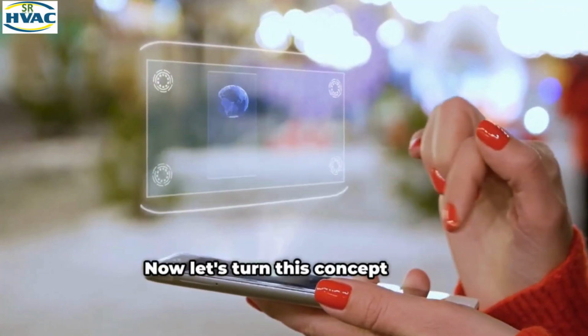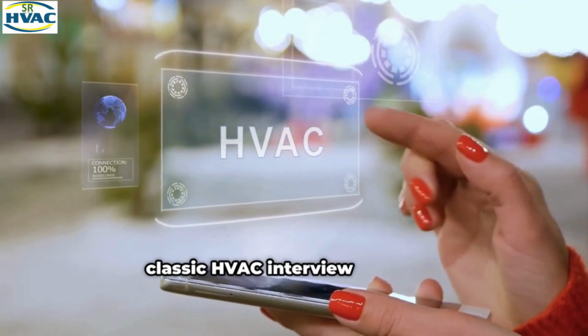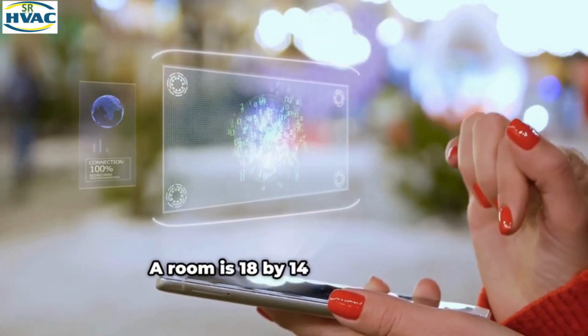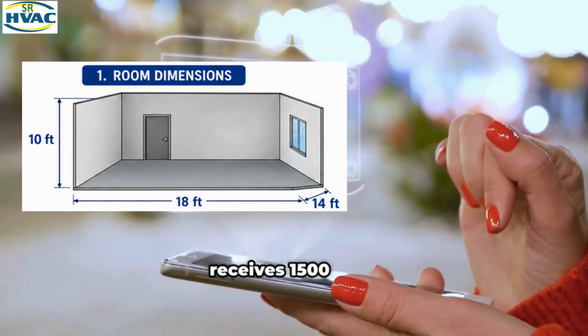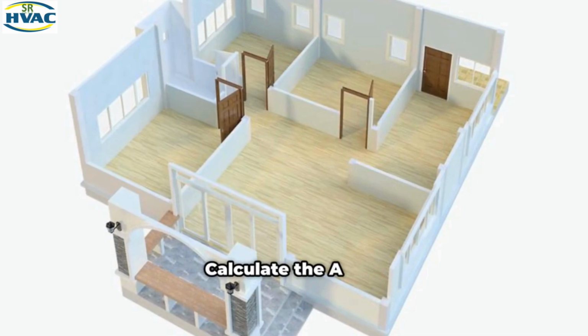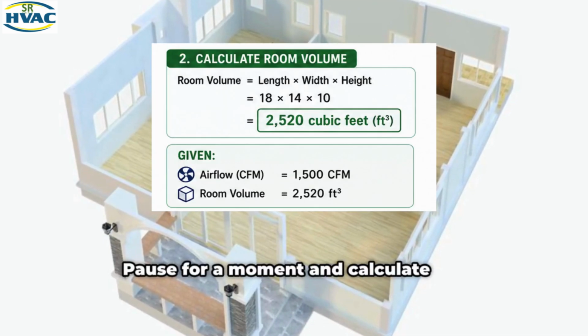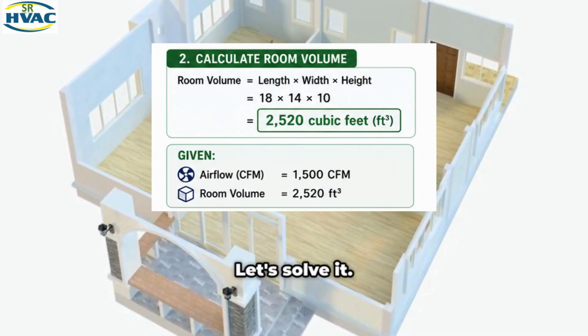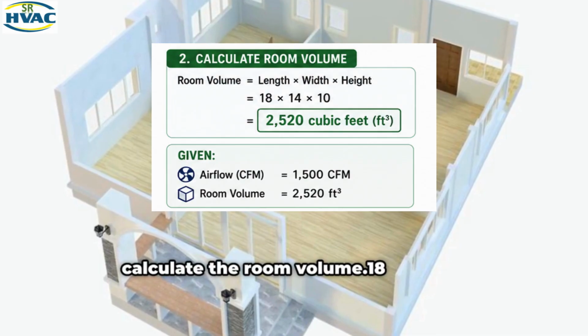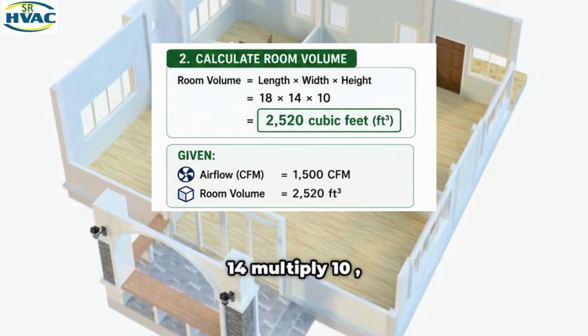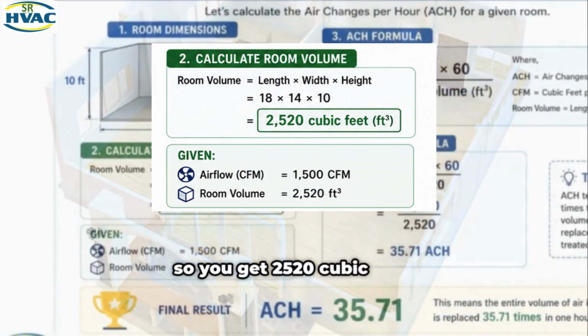Now let's turn this concept into a classic HVAC interview question. A room is 18 by 14 by 10 feet and receives 1500 CFM. Calculate the ACH. Pause for a moment and calculate the answer yourself. Let's solve it. First, calculate the room volume. 18 multiplied by 14 multiplied by 10, so you get 2520 cubic feet.